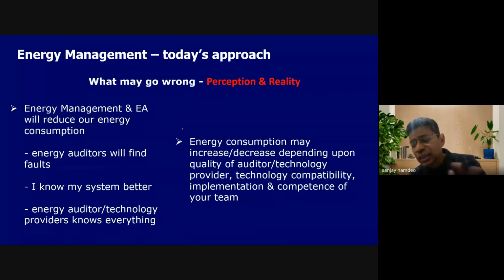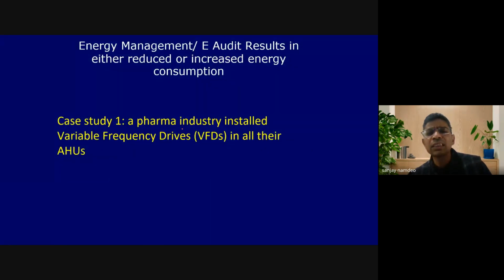So there have been many reasons. I will just share a very simple case study. Many of you might be aware of the variable frequency drive, which modulates the speed of any equipment. When the speed is changed, the output of that equipment will change, and if the output changes, the power consumption will also change. One common issue in industry is that most equipment is oversized or designed for the peak load, but that peak load happens only for 10 to 20% of the time. So most of the time, the equipment runs in underloading condition.